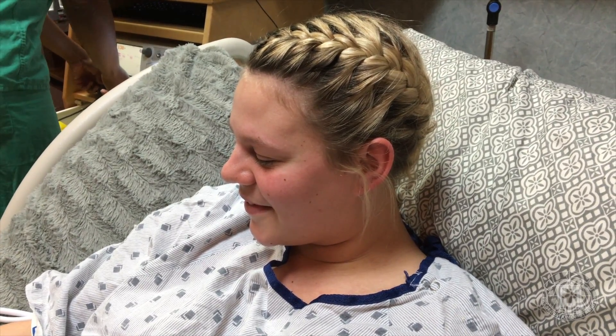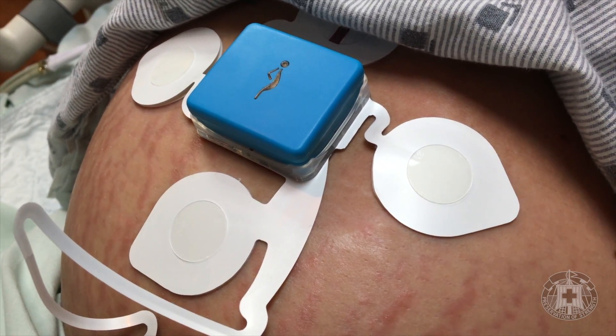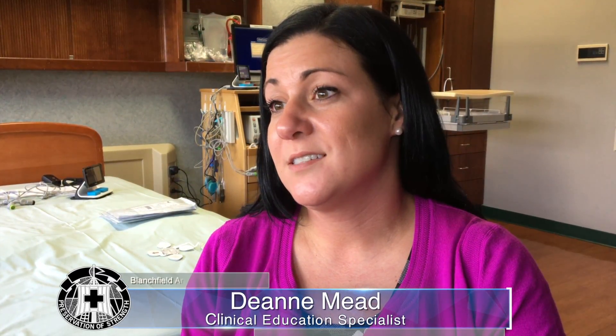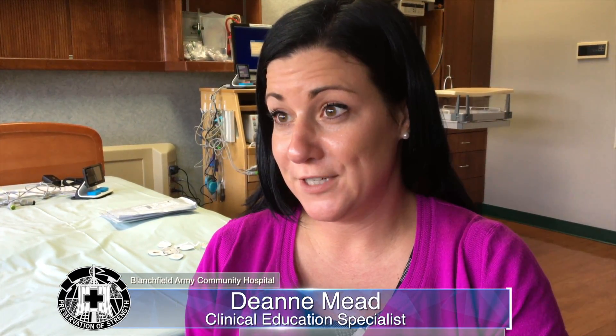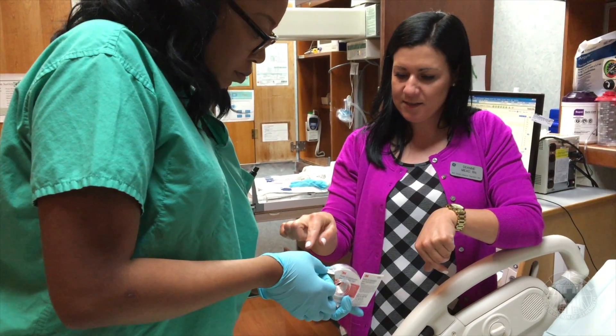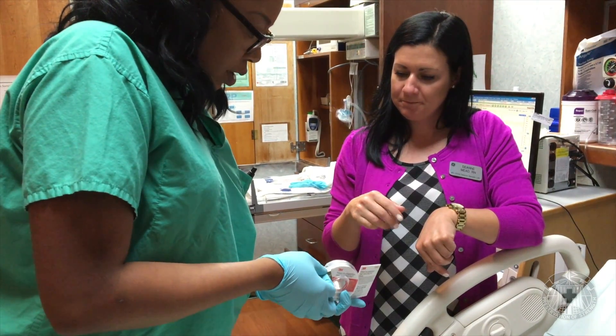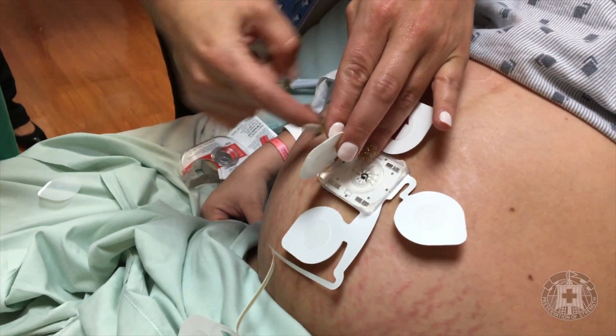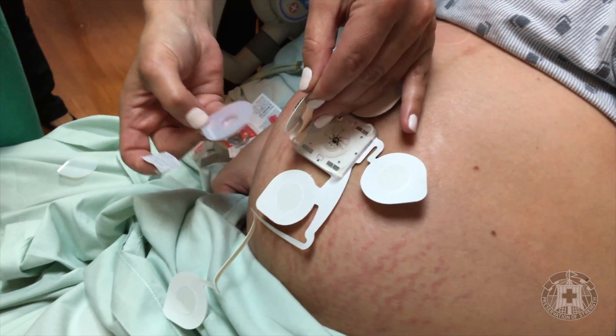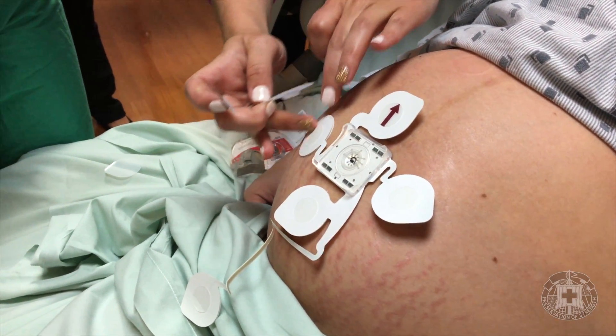The system is based off the belly button on the patient. It's a patch that sticks on, and then there's a little pod that hooks into it, and it'll monitor mom's heart rate and baby's at the same time. It's very beneficial for high BMI patients because adipose tissue is a conductor for ECG, so it helps a lot with higher BMI patients that are difficult to monitor with ultrasound. It's also an option for patients that were difficult to monitor with FSE or ultrasound.